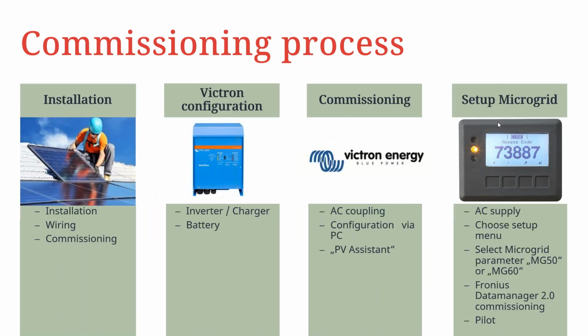So when it comes to the commissioning process of the AC coupled installation, it's quite easy. Once you have done the installation and the wiring, you have to commission separately both the Victron and the Fronius inverters. So for the Victron inverter, you'd have to go through the various assistant wizards, and you would have to configure, for example, the PV assistant or the ESS, depending on which particular application you are doing.